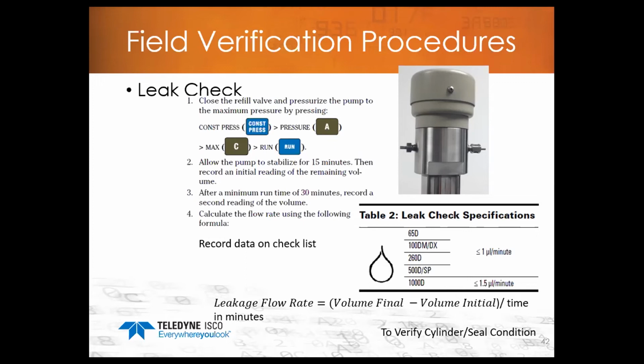And then after that 15 to 30 minutes, once it's stabilized, you're going to record a volume reading on the display of the controller. You'll record that volume reading, and then you'll continue to let the pump run for at least 30 minutes. I would recommend maybe an hour, maybe even 2 hours. Just let the pump run under that constant pressure condition as far as the leak check is concerned.